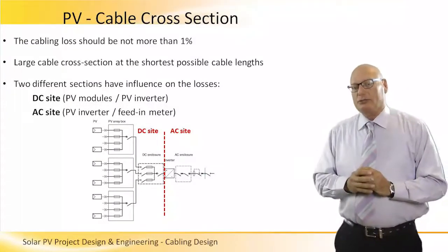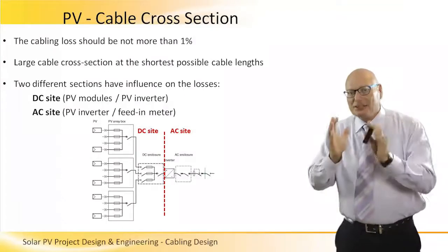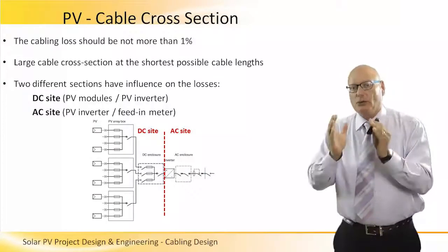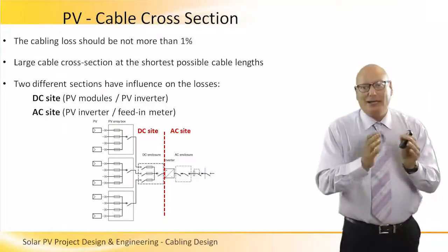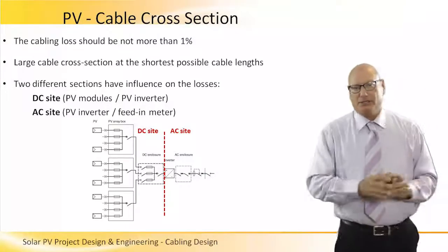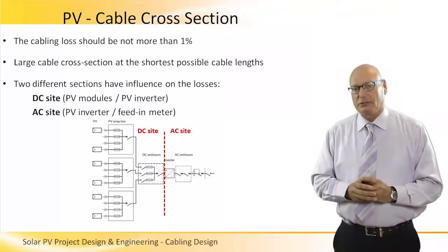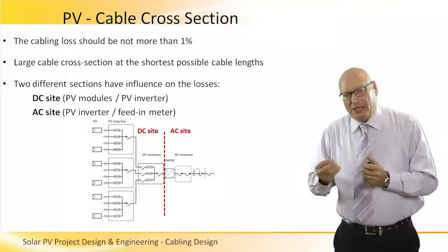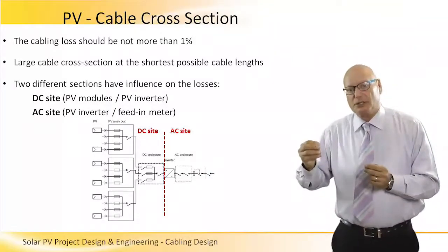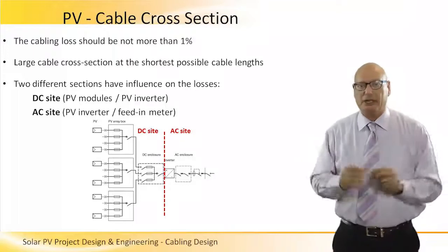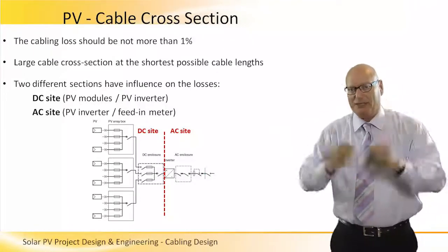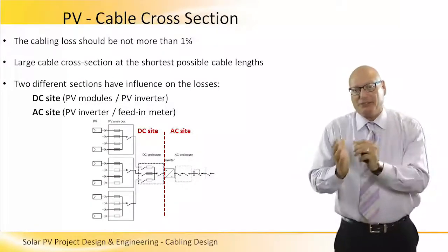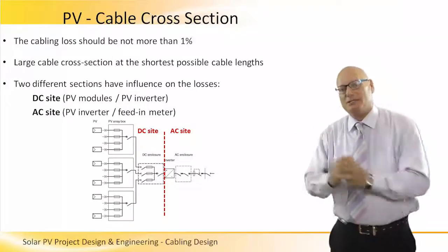Now, cable cross-section. As a target, we would like to have the loss less than 1% because of the cables. Ideally, we want the largest cable cross-section at the shortest possible cable length. We have two sides: the DC side and the AC side.